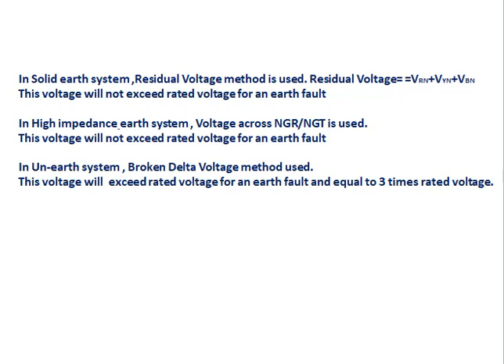In summary: in a solid earth system, the residual voltage method is used (Vrn + Vyn + Vbn), which will not exceed rated voltage for an earth fault. In a high impedance earth system, the voltage across the NGR or NGT is used, also not exceeding rated voltage. In an unearthed system, the broken delta voltage method is used, which exceeds rated voltage and equals three times the rated voltage for an earth fault.